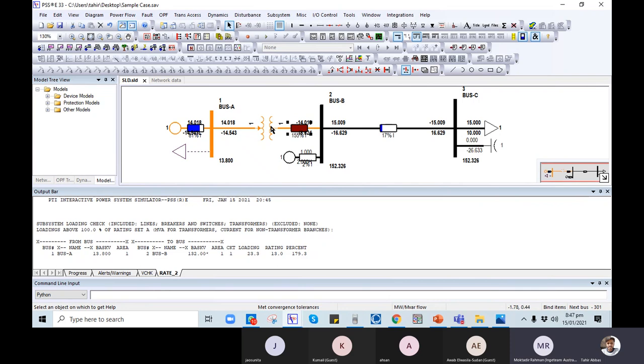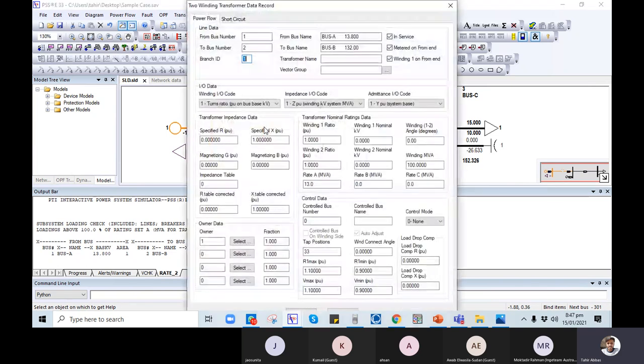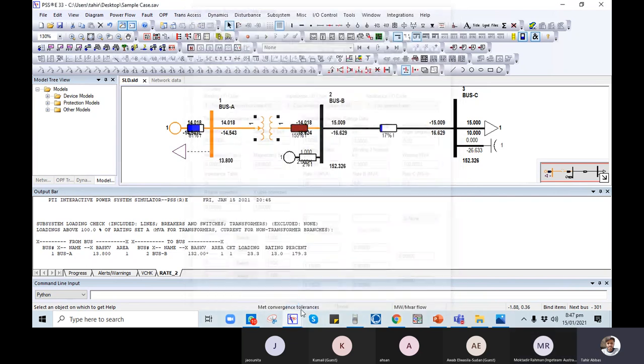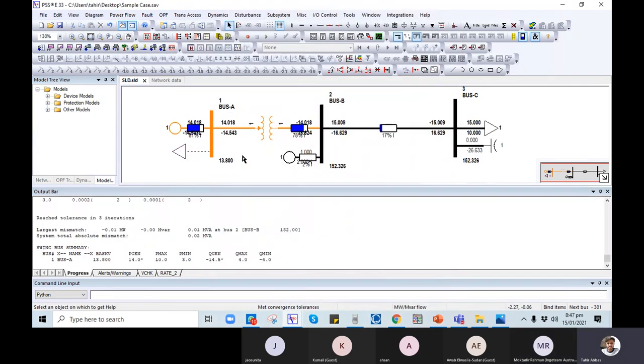So it means that this is 55% overloaded, not 155. At 100%, it means it is maximum loading. 155 means it is loaded 55%. So what I will do, I will augment the transformer to 26 MVA, or I will add a parallel transformer. Now you can see that 78. Okay. This is how you check the thermal violation.